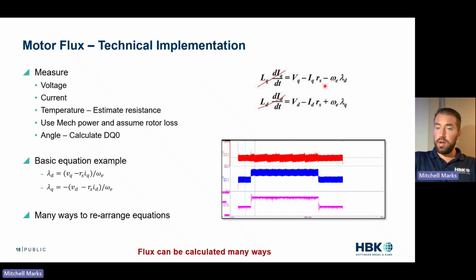So we look at the technical implementation. You can go through some equations and look at some math and figure out what your flux is. And from a measurement standpoint, we measure voltage and current, V and I. We can look at temperature to estimate resistance. Or in a measurement test stand, we can use mechanical power to assume rotor loss and kind of manipulate this equation. There's some clever stuff. We can discuss that. And then we have the speed of the unit. We can rearrange these equations to get our flux. So a basic example is, lambda equals V minus losses over speed. And what we end up doing is DQ0 calculations for voltage, DQ0 for current, which I have displayed here. Our software can calculate that in real time and display that as a scope trace.